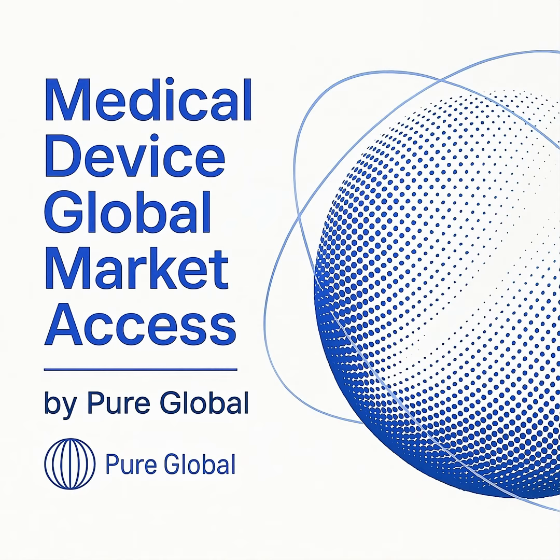It introduced EUDAMED and Unique Device Identifiers, UDI, for traceability, defining obligations for economic operators. The EU IVDR specifies 4 types: manufacturers, importers, distributors, and authorized representatives. Each economic operator has obligations under EU IVDR Articles 10 to 16, applicable since May 2022, to all EU-marketed IVDs, including legacy devices, per MDCG 2022-8.